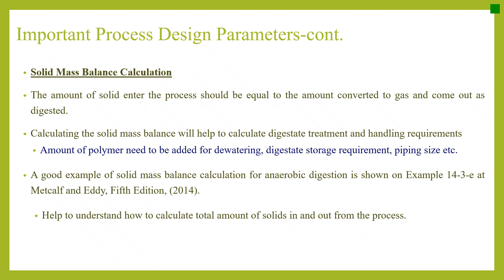For solid mass balance calculations, the amount of solids entering the process equals the amount converted to gas plus the amount coming out as digestate. Calculating the solid mass balance helps determine digestate treatment and handling requirements — such as the amount of polymer needed for dewatering, digestate storage requirements, and piping sizing. A good example of solid mass balance calculation for anaerobic digestion is shown in Example 14.3 of Metcalf and Eddy, 5th edition.